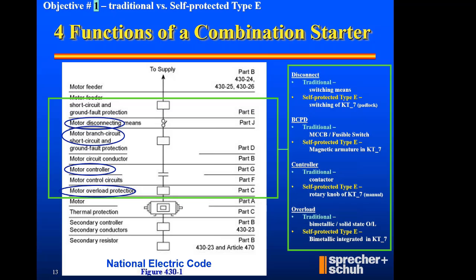So, redefining in the National Electrical Code, figure 430-1 identifies the illustration of all the necessary means. At the very top, it's got to have some sort of a means of disconnecting. On the right-hand margin, from a disconnect perspective, I'm breaking down the comparison: how would we comply with a disconnect from a traditional means versus a self-protected means? From a disconnect, the traditional means, there's going to be a handle. There's going to be a way of turning the disconnect on and off. So the handle takes care of that.